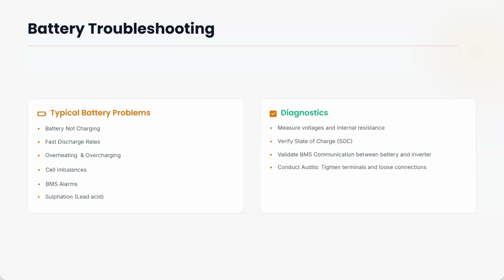So you record all this, then verify the state of charge. Does it really get fully charged? What's the terminal voltage at that time? So you get all that. Validate the BMS communication between battery and inverter. Are they really communicating, or has the communication process been disconnected? Is it that the cable has pulled out, or the inverter settings have changed, or probably somebody has tampered with it and then the battery no longer communicates? Then it's a problem. So conduct audits, tighten terminals, and loose connections.